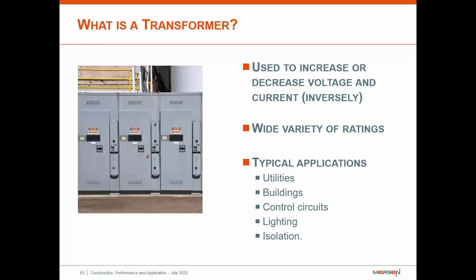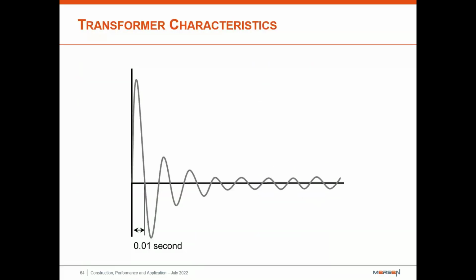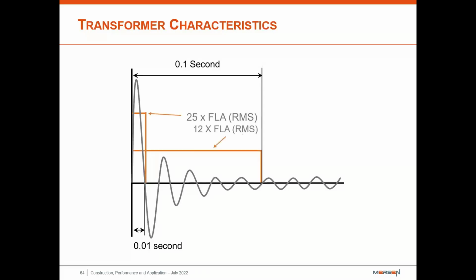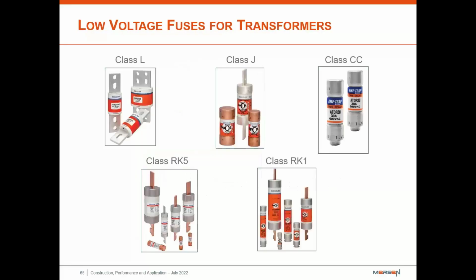So what is a transformer? It's used to either increase or decrease voltage and current inversely. There's going to be a wide range on these, but for us, we're just going to focus on certain kinds of applications. So with that, we're going to go with the 0.01, which is going to be 25 times the FLA (RMS). For 0.01 seconds, you're going to be at about 25 times the FLA. So when you're sizing these, you want to make sure that your time current curve is to the right of whatever's coming in. And we'll take a look at this in a second. You're going to want, for 0.1 seconds, 12 times the full load amp. So what style of fuses do we actually have for this? We have our L's, J's, CC's, RK5s, and RK1s.